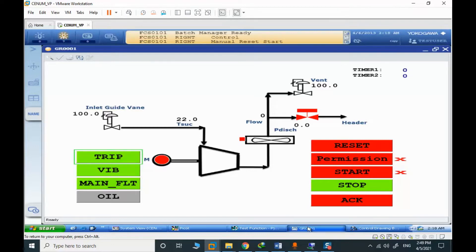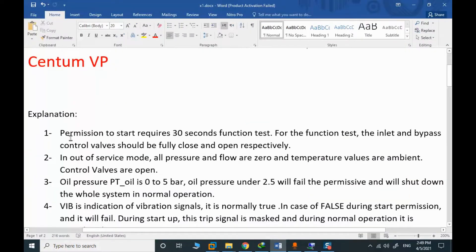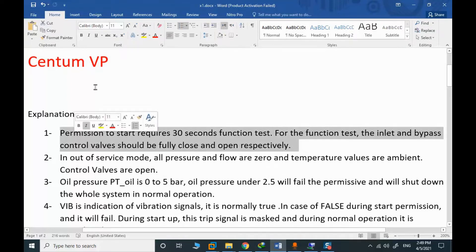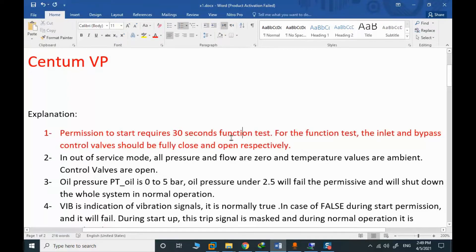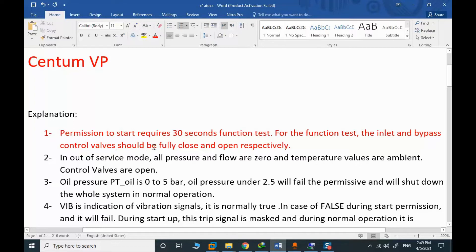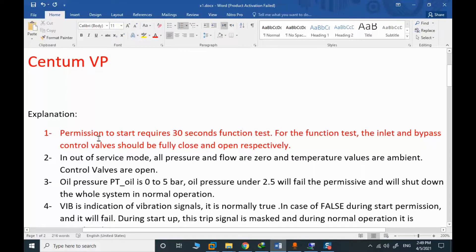We start with the permission. Permission to start requires 30 seconds. Function test. We check for the function test, the inlet and bypass control valve should be fully open and fully closed and open respectively. The IGV inlet valve is fully closing during permission.